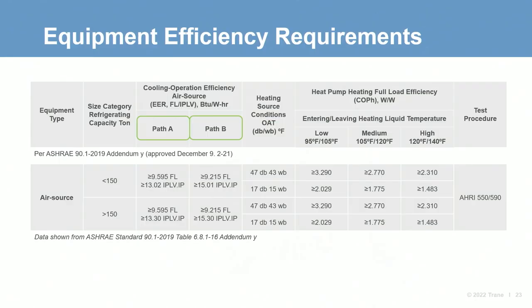Recall that heat pumps operating in cooling mode are less efficient compared to chillers, so the cooling requirements for heat pumps are lower than that of chillers. Note that if the heat pump will only be used as a heating-only unit, it does not have to comply with either cooling efficiency path. On to the new stuff. Now we have the addition of heating mode requirements.